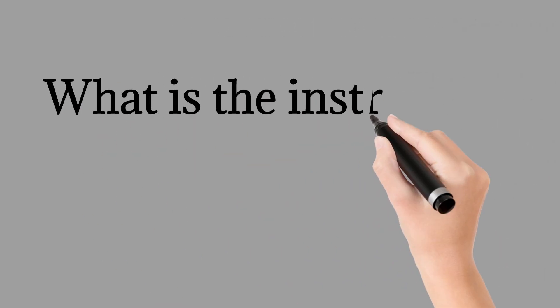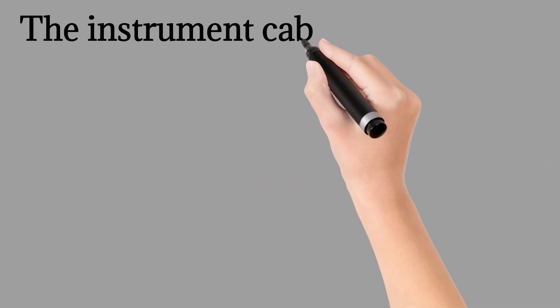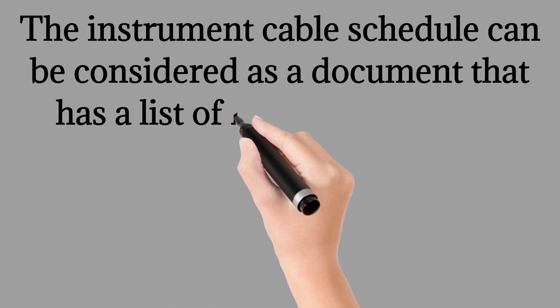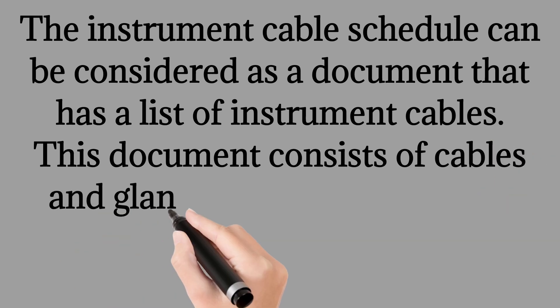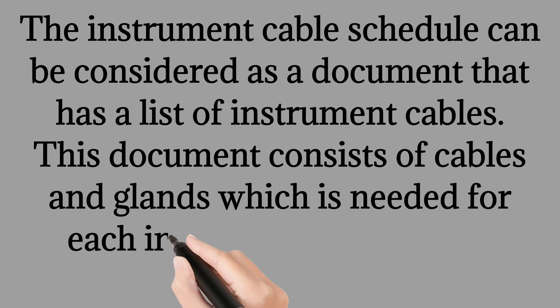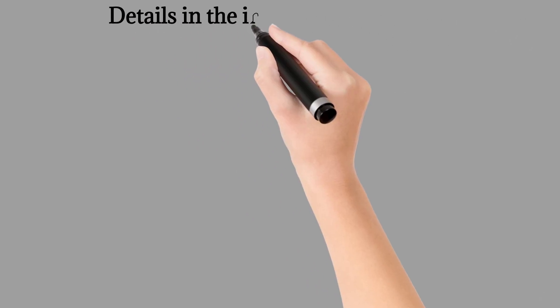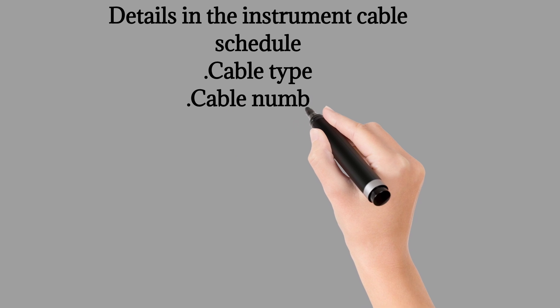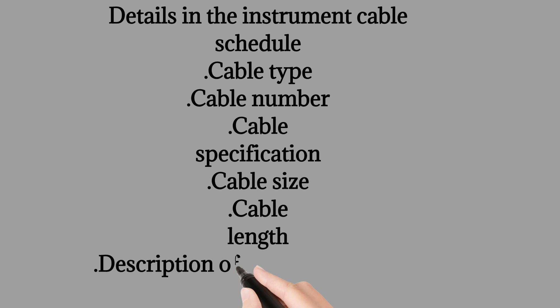What is the instrument cable schedule? The instrument cable schedule can be considered as a document that has a list of instrument cables. This document consists of cables and glands which is needed for each instrument connection. Details in the instrument cable schedule include cable type, cable number, cable specification, cable size, cable length, description of the source and the destination, cable gland, and also the size of each cable.